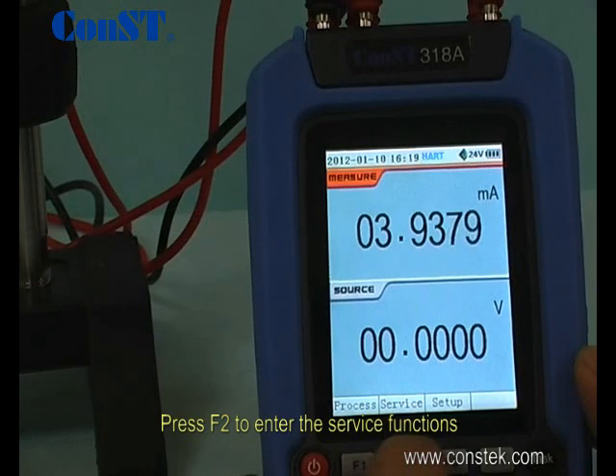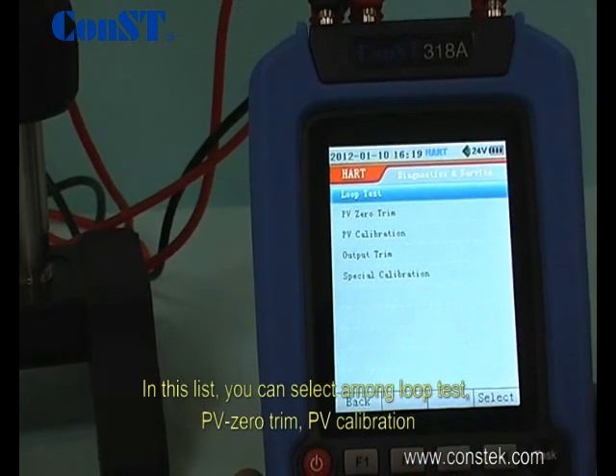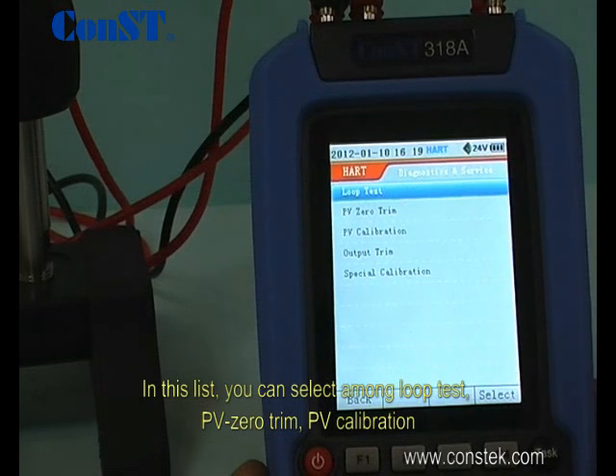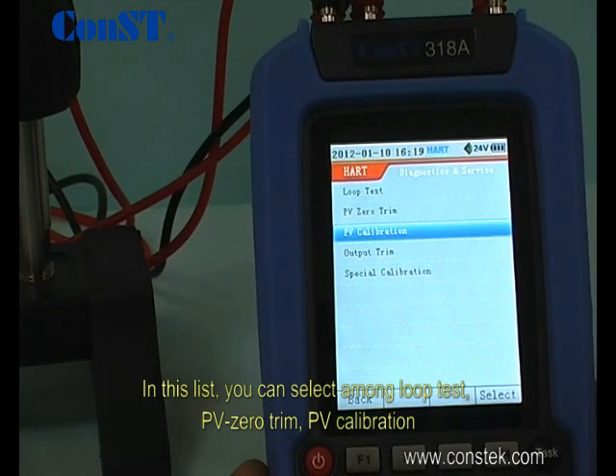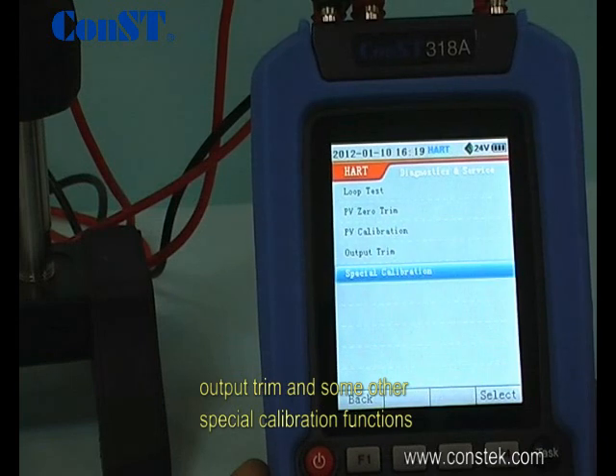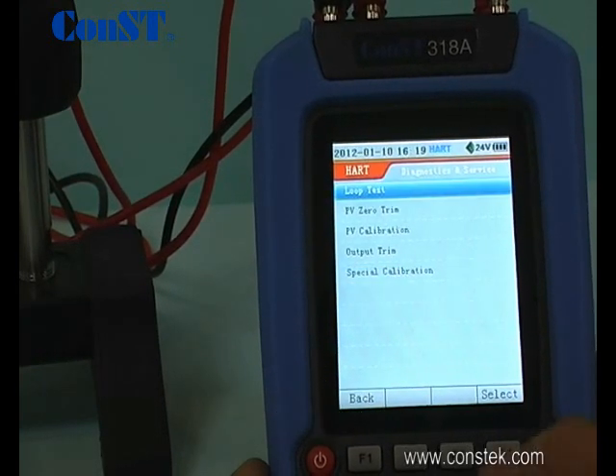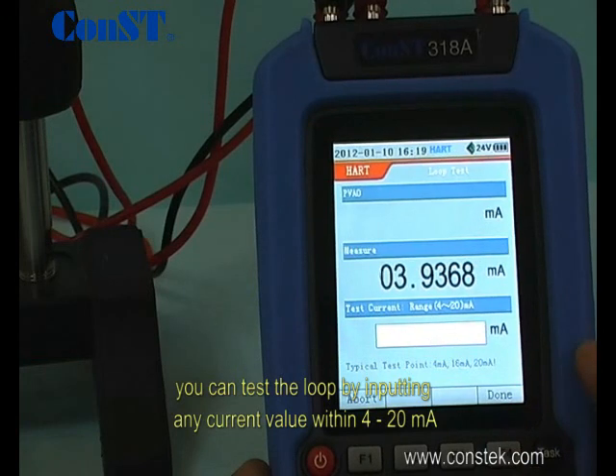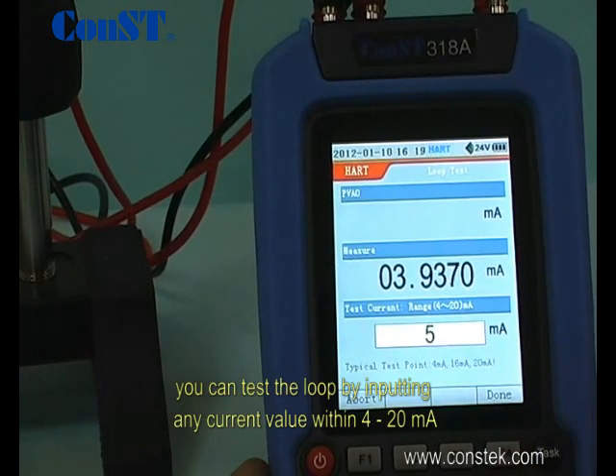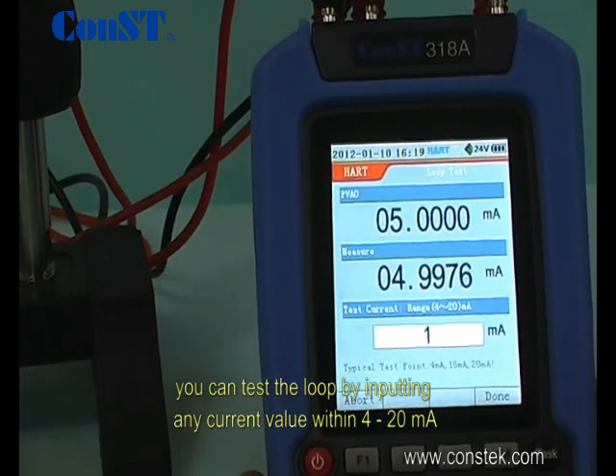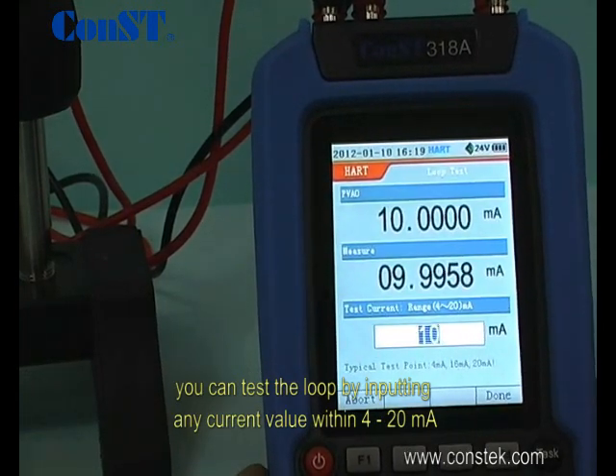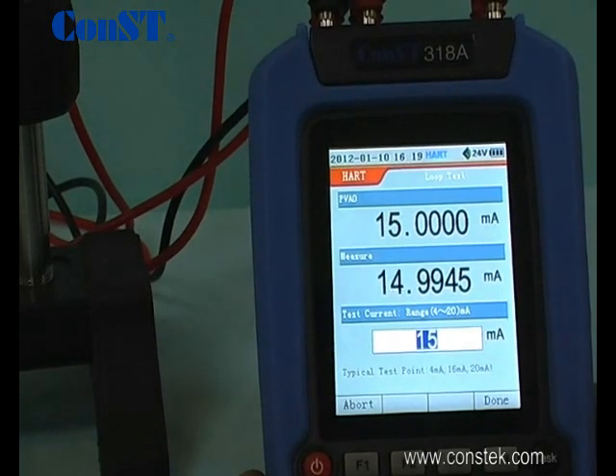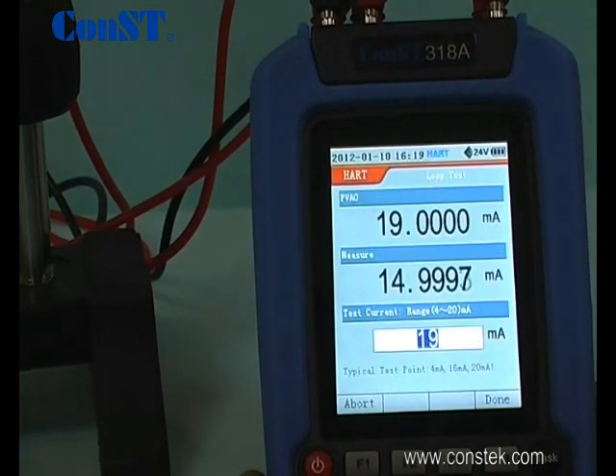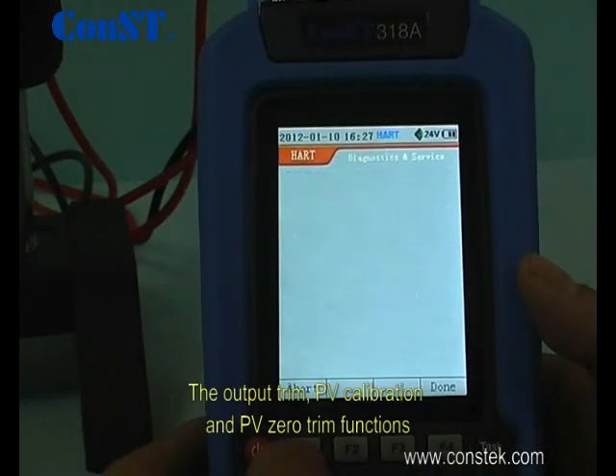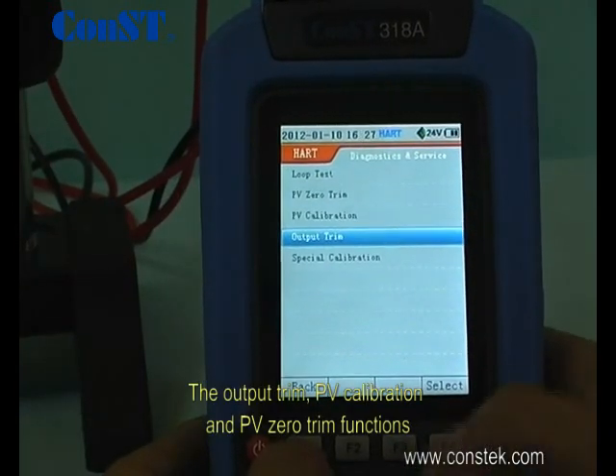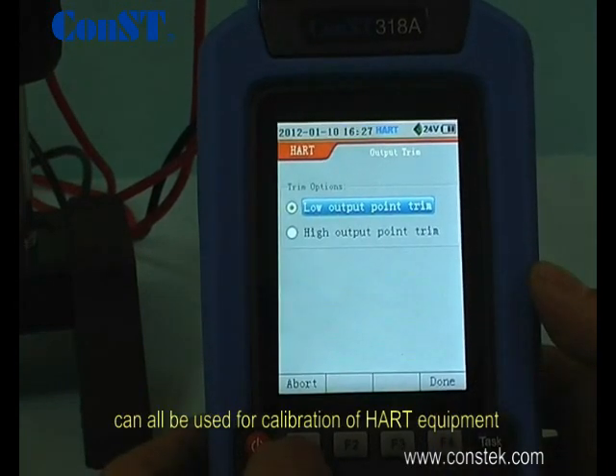Press F2 to enter the service functions. In this list, you can select among Loop Test, PV Zero Trim, PV Calibration, Output Trim, and some other special calibration functions. In the Loop Test, you can test the loop by inputting any current value within 4 to 20 milliamps. The Output Trim, PV Calibration, and PV Zero Trim functions can all be used for calibration of HART equipment.